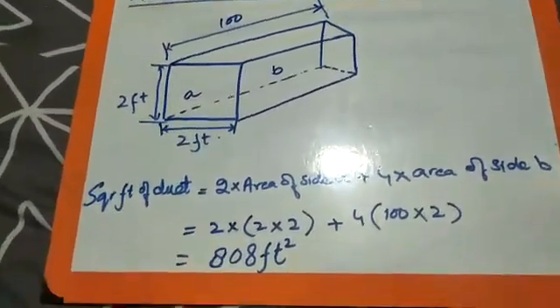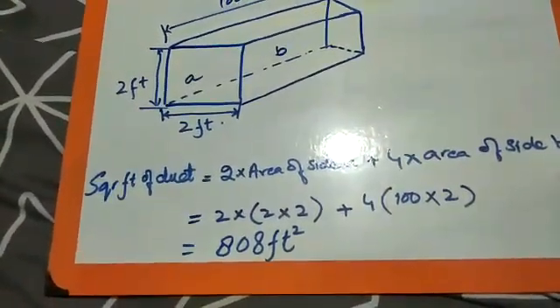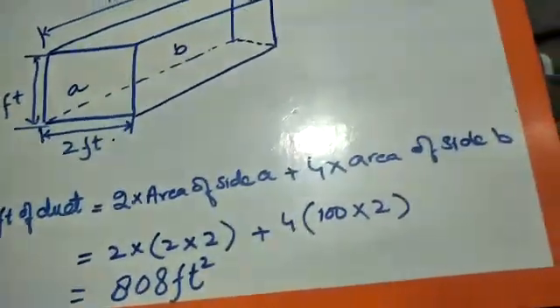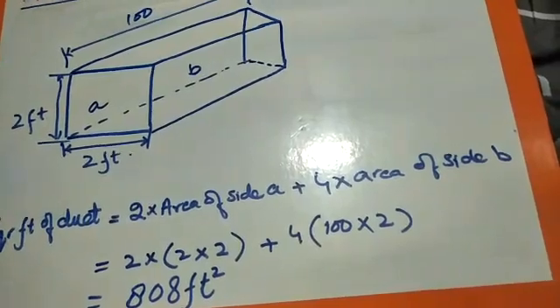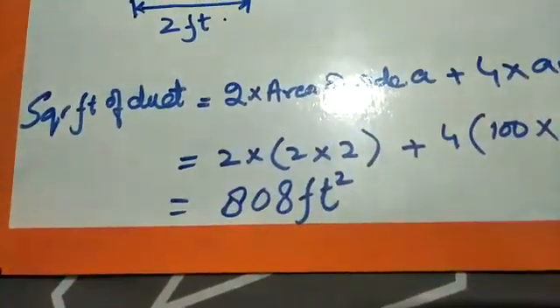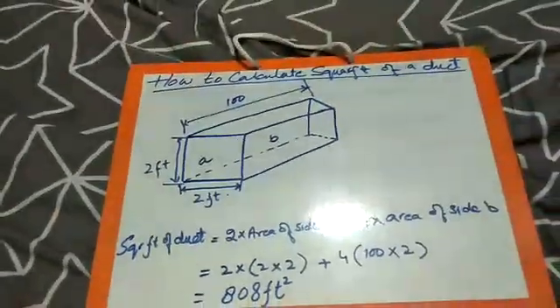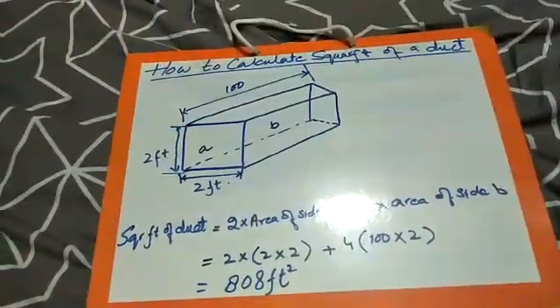Putting the values: 2 multiplied by area of side A, which is 2 feet by 2 feet, plus 4 times the area of side B, which is 100 by 2 feet. So the square feet of duct will be 808 square feet. This was a simple technique for calculating the square feet of a square duct.